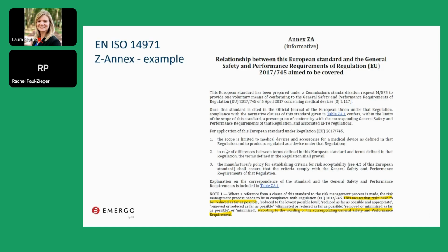Here you have an example of Annex Z for the standard about risk management process, 14971. So you can see here that reference is made to the MDR and there are additional requirements clearly stated here. And then you have a table providing a little more details.